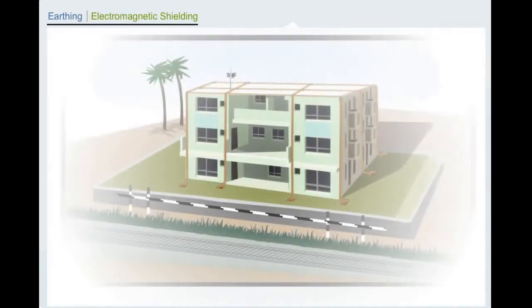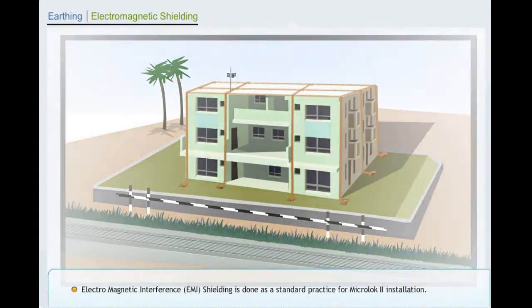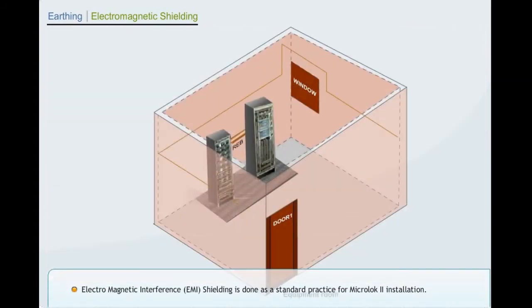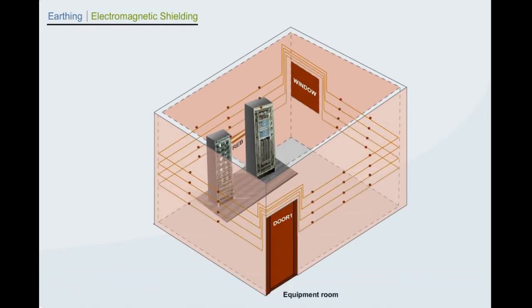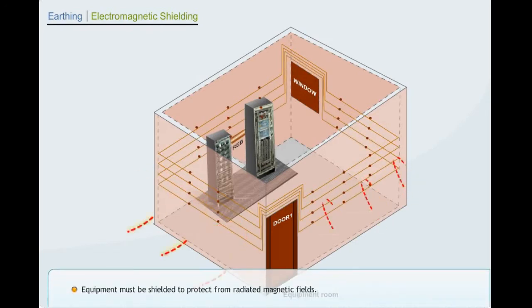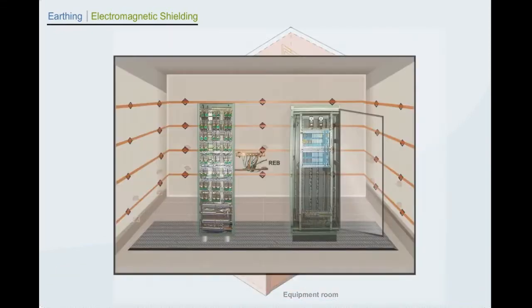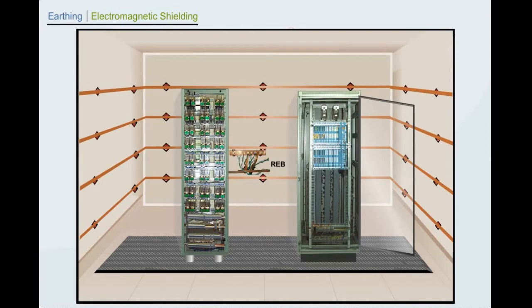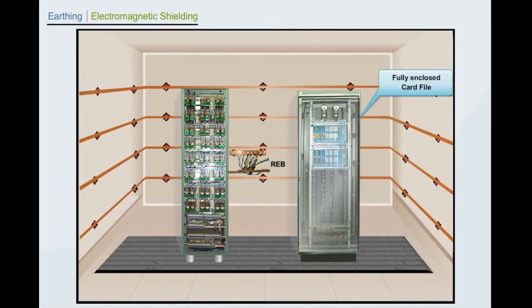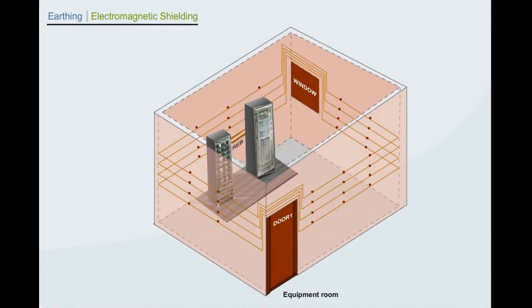Earthing, electromagnetic shielding. Electromagnetic interference shielding is done as a standard practice for Microlok 2 installation. Equipment must be shielded to protect from radiated magnetic fields. Shielding can be achieved by locating the equipment in card file with fully enclosed as possible by means of appropriate external enclosures under consideration for the equipment.